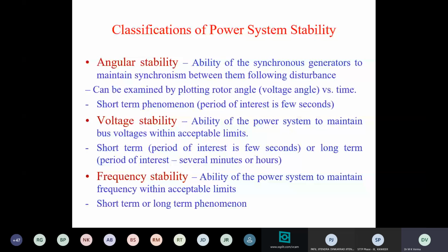Long-term means it may take several minutes or hours, but it may also be a short-term phenomenon where voltage instability may occur in a few seconds. This occurs particularly when we have dominance of induction motor dynamics, HVDC converter dynamics, and power electronics equipment, all these FACTS controllers. If these dynamics are dominant, then similar to angular oscillation, there may be voltage oscillation also, and it may become unbounded in case of instability.